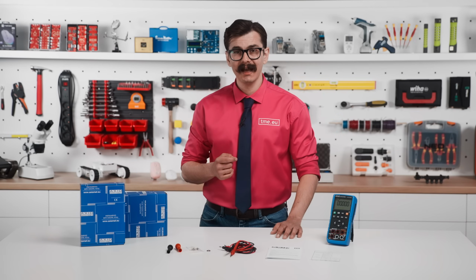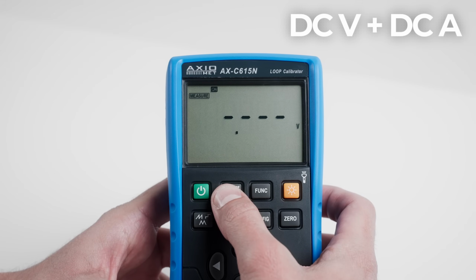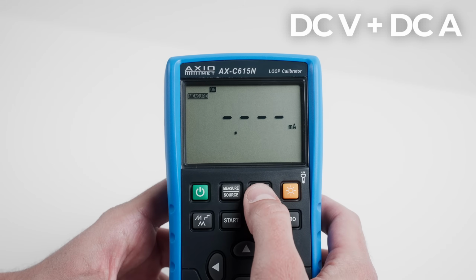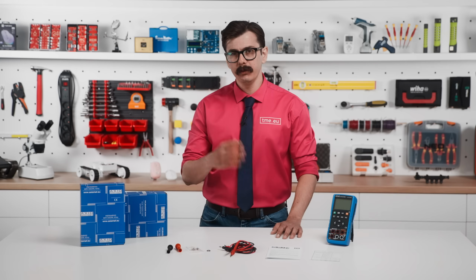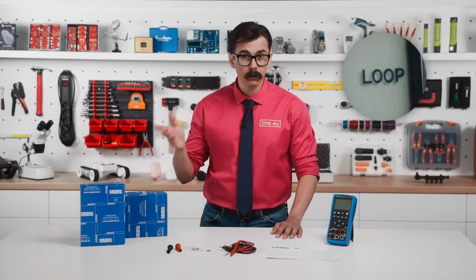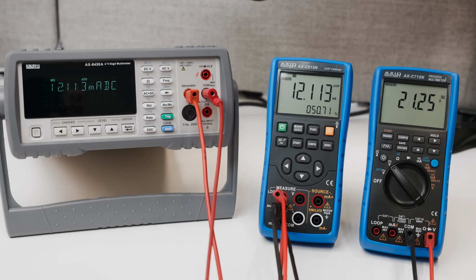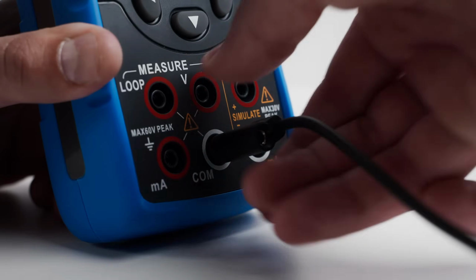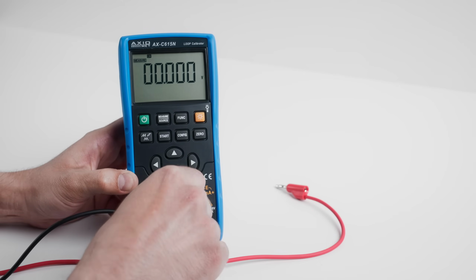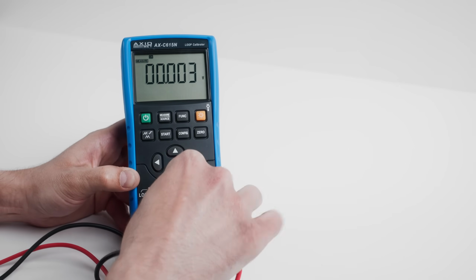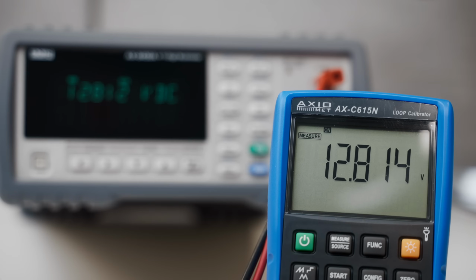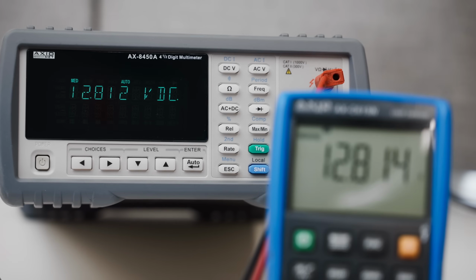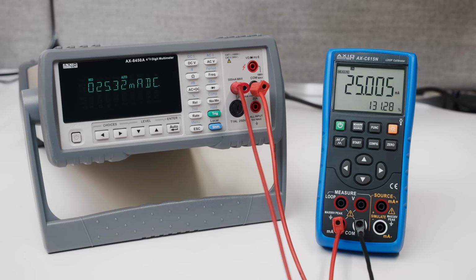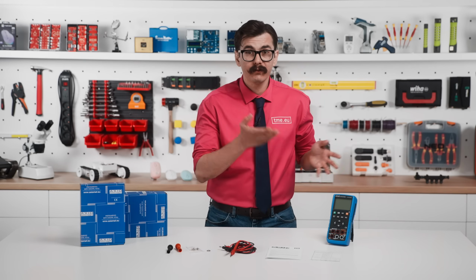For DC voltage and DC current measurements, first switch to the measure function using the measure source button, and then select voltage or current using the function button. As you may have noticed, there is another measurement option called loop. This allows you to measure the current while also supplying the device under test with 24 volts DC. All measurements are performed using the left side terminals. Black probe goes to the COM, red probe goes to the voltage, milliamps or loop terminals depending on the measurement. Although this device is not a full multimeter, these simple measurements can help you determine whether the transmitter outputs the correct current or whether the loop power supply is present, and even test the PLC input for correct signals.